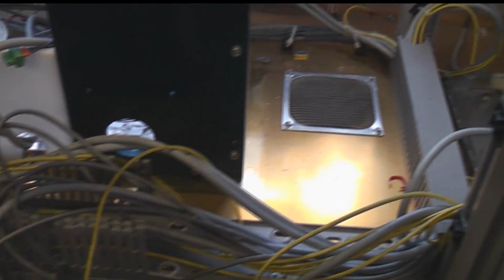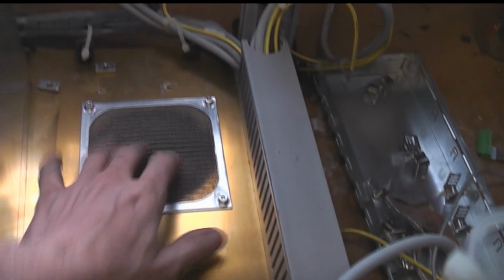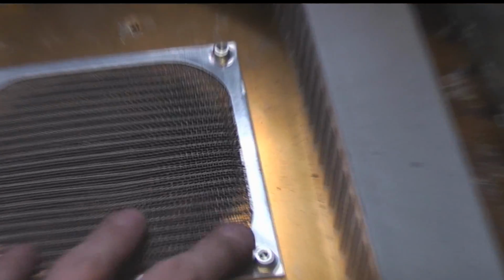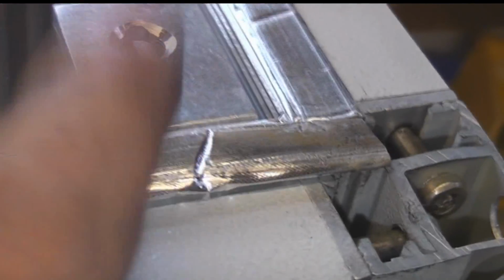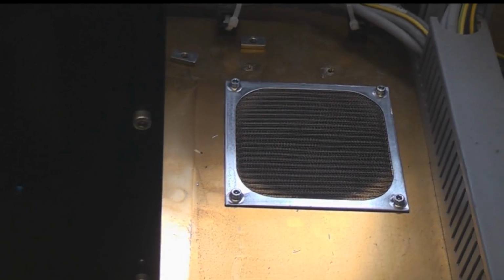So there's lots of attention to shielding. For example, this is just an air filter to let the air go out, but that's got shielding mesh over it. In the top cover again we've got this RF gasket, and you see they've put a gap in the paint on there, so they were very serious about shielding on this thing. Obviously the sensor itself is sensitive, but that's going through coax cable, so it's probably just generally EMC and belt and braces, stop anything getting in or anything getting out.